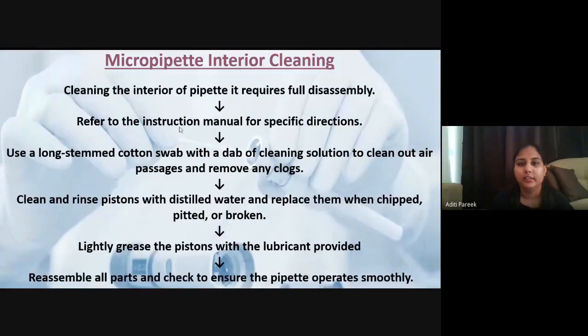For the interior cleaning of the micropipette, we just have to disassemble the whole structure, and this can be done by reading the instruction manual provided with the micropipettes. After disassembling it, we can use a long stem cotton swab with a dab of cleaning solution to clean out air and remove any clogs. We should also clean and rinse the piston with distilled water and replace it if it is chipped, pitted, or broken. Lightly grease or lubricate the O-ring with the lubricant provided, reassemble all the parts, and check whether it operates smoothly or not.